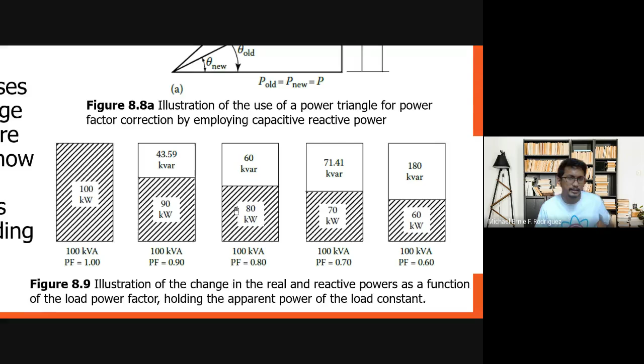Dito naman, take note that sa 80% power factor, your reactive power is large, malaki na yung kilovars. So ang nangyari, you have now 25% increase in the total apparent power of the line, tumataas yung kVA ng line natin. So at this power factor, your 75 kVAR of capacitor is needed to cancel the 75 kVAR of the lagging component. So yun yung power factor correction.